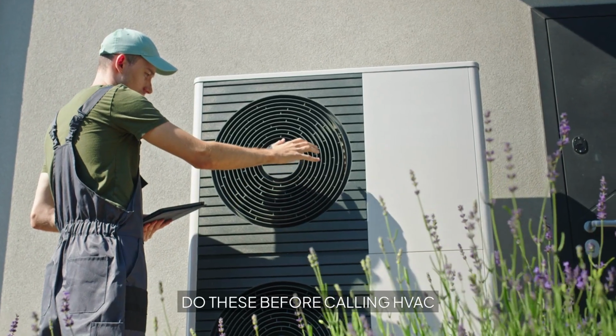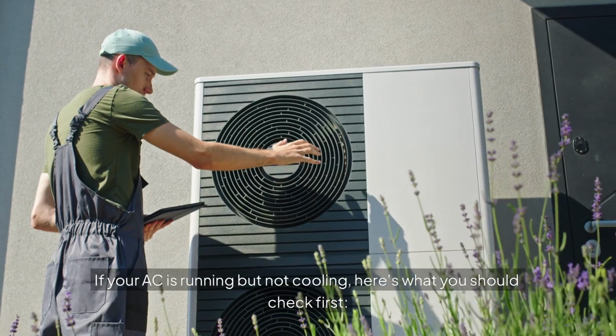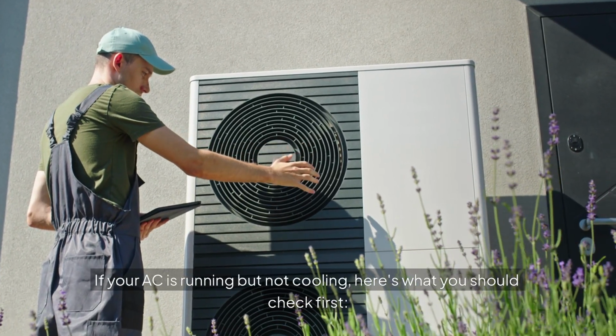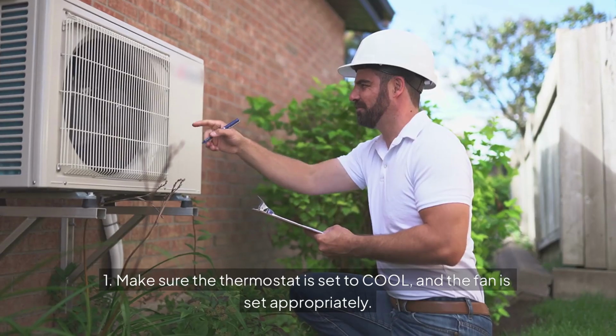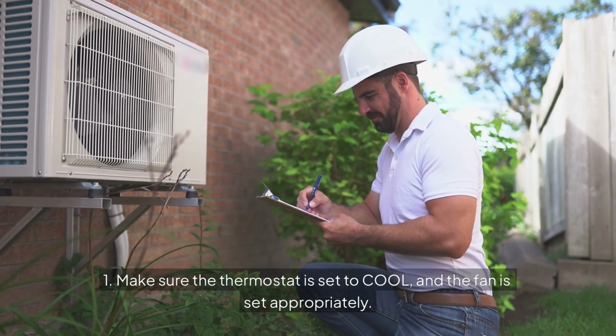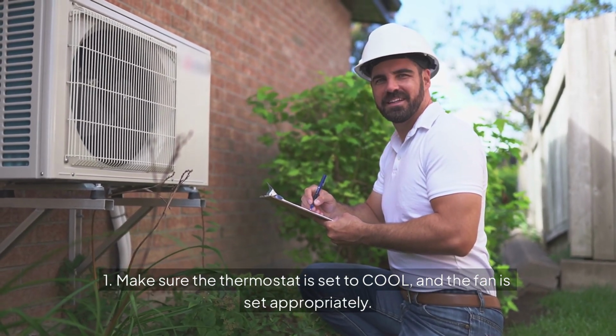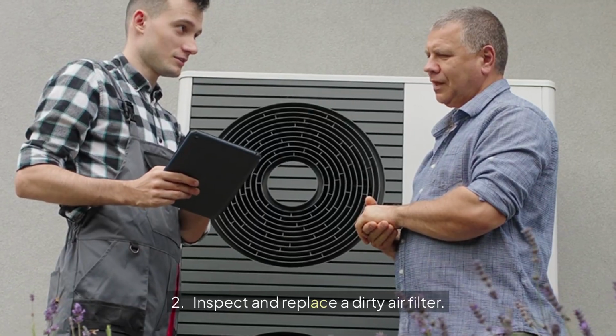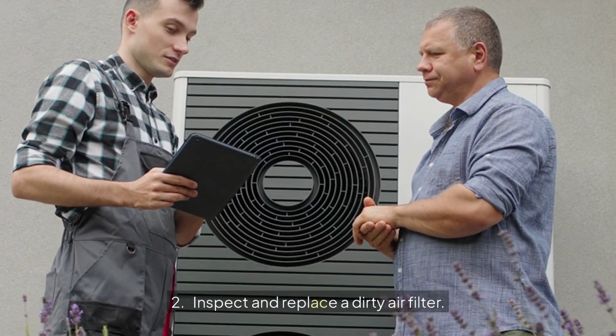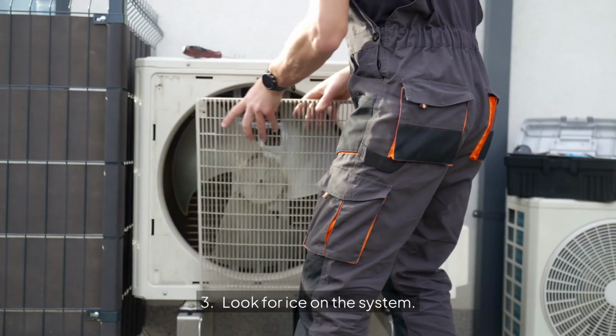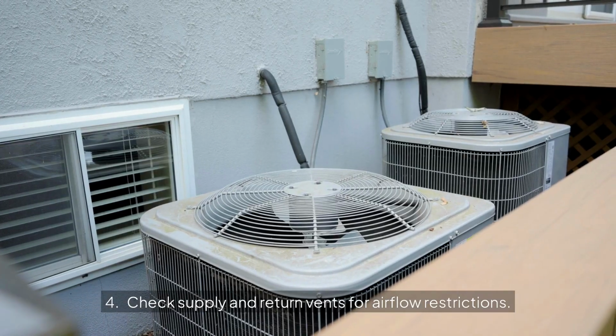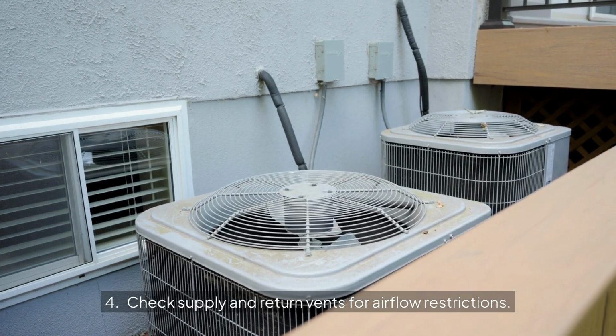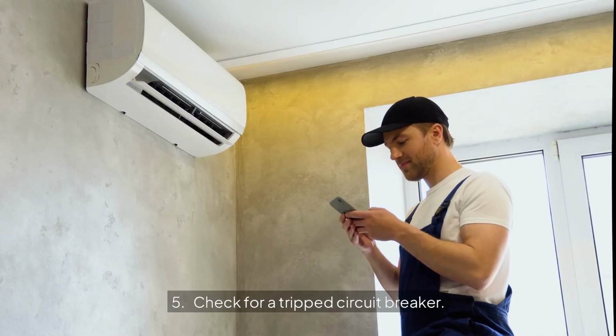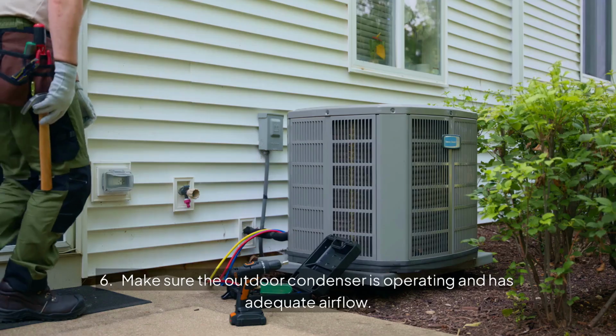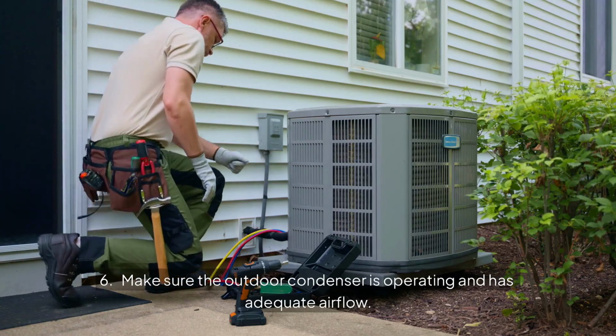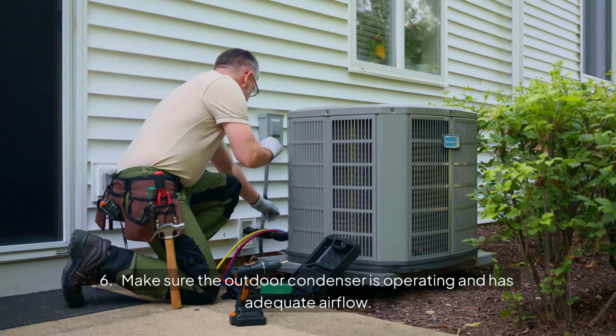Do these before calling HVAC. If your AC is running but not cooling, here's what you should check first. 1. Make sure the thermostat is set to cool and the fan is set appropriately. 2. Inspect and replace a dirty air filter. 3. Look for ice on the system. 4. Check supply and return vents for airflow restrictions. 5. Check for a tripped circuit breaker. 6. Make sure the outdoor condenser is operating and has adequate airflow.